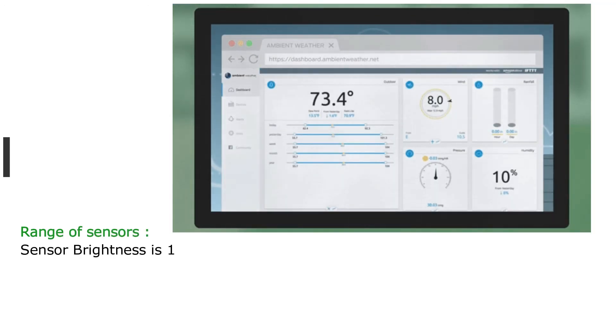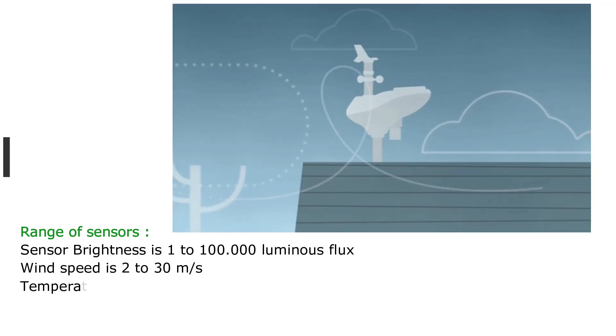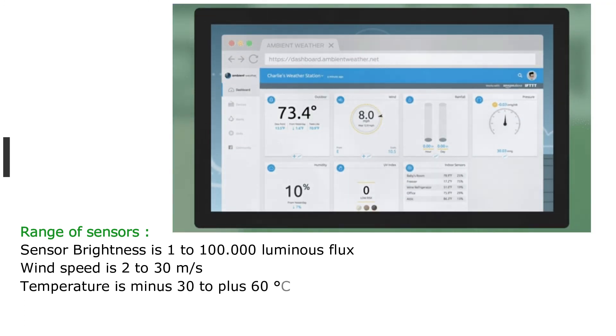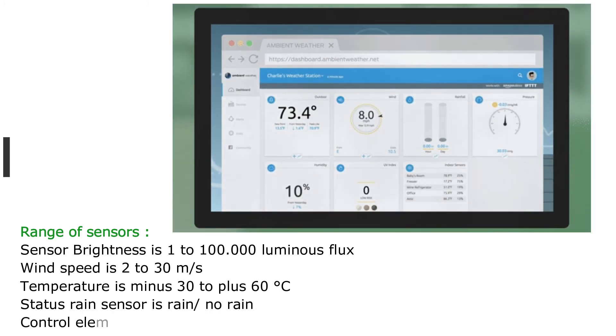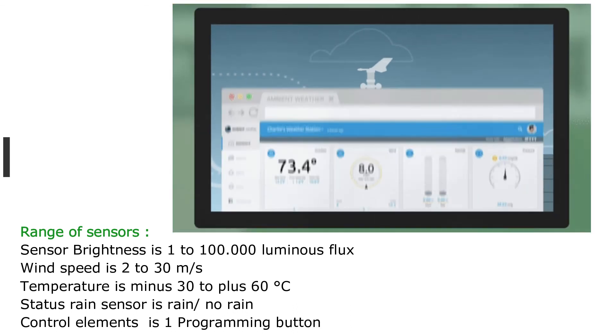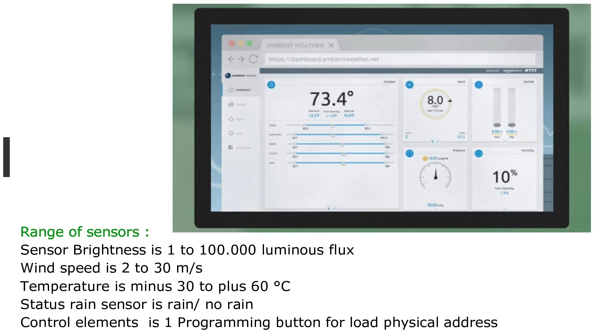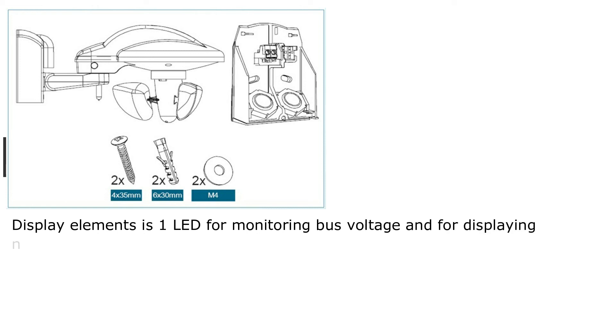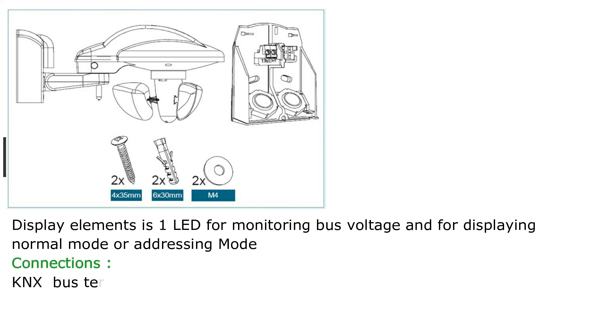Sensor ranges: brightness is 1 to 100,000 lux. Wind speed is 2 to 30 meters per second. Temperature is minus 30 to plus 60 degrees Celsius. Rain sensor status is rain or no rain. Control elements: 1 programming button for loading the physical address. Display elements: 1 LED for monitoring bus voltage and displaying normal mode or addressing mode. KNX bus terminal accepts wire diameter 0.6 to 0.8 mm with strip insulation of 5 to 6 mm.